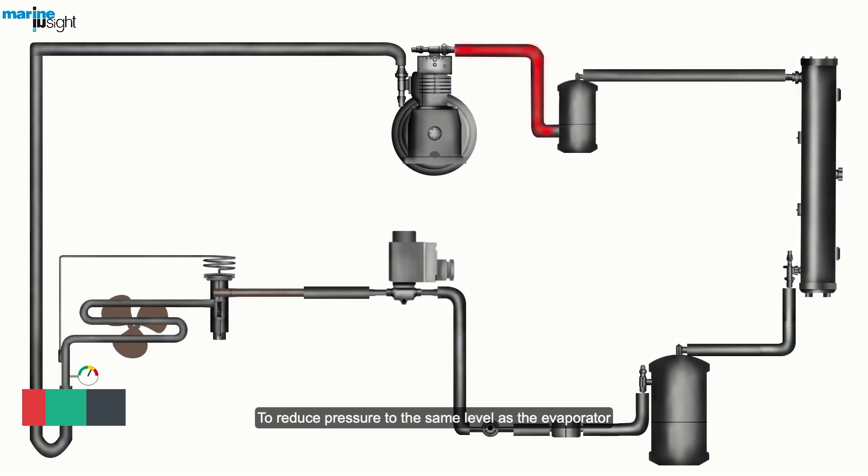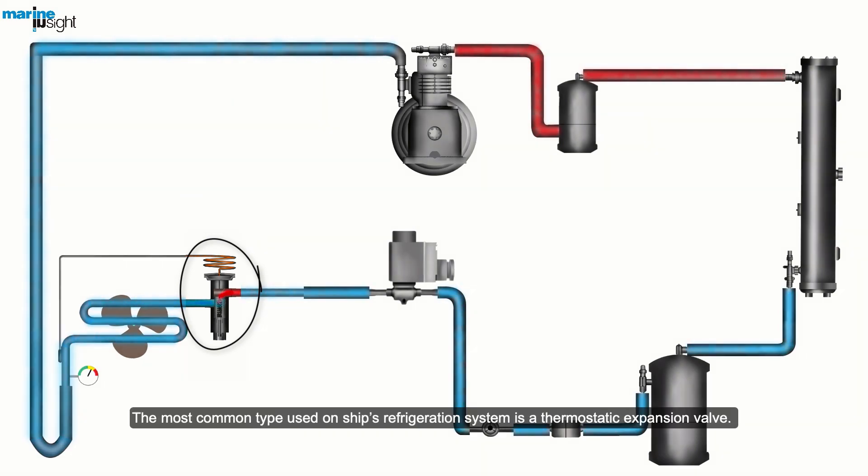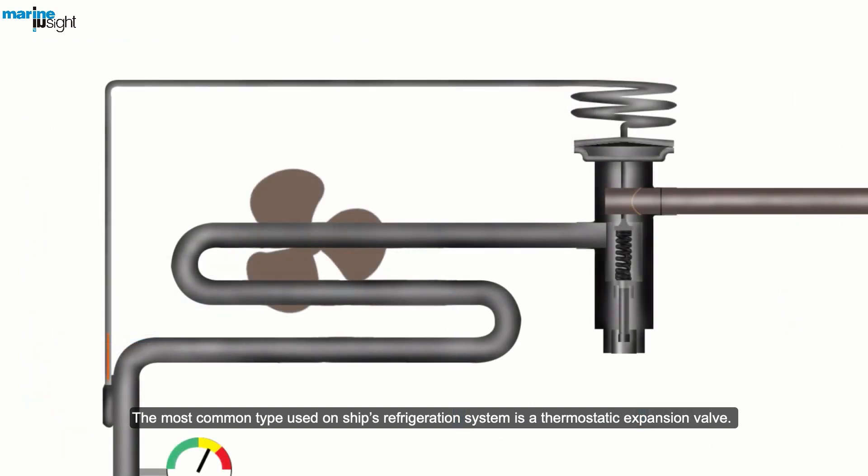To reduce pressure to the same level as the evaporator, a device must be inserted to carry out this process, which is called throttling or expansion. This device is a throttling or expansion valve. The most common type used on ships refrigeration system is a thermostatic expansion valve.